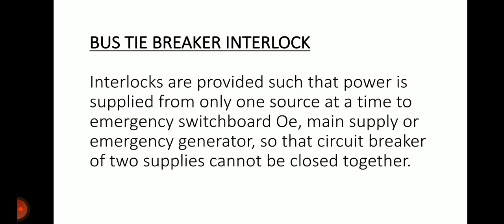The tie breaker is provided in the bus bar with interlocks so that power is supplied from only one source at a time. You cannot run from the main generator and emergency generator simultaneously. This bus bar tie breaker ensures only one source — main supply or emergency generator — is active at a time. If both circuit breakers were closed simultaneously, a total blackout would occur from which recovery is not possible. With this interlock technique, when the main supply fails, the emergency generator can be activated.